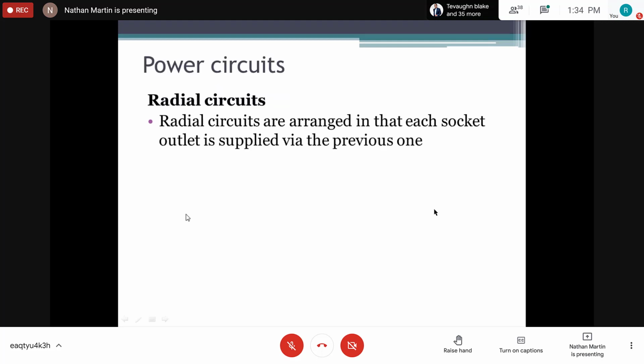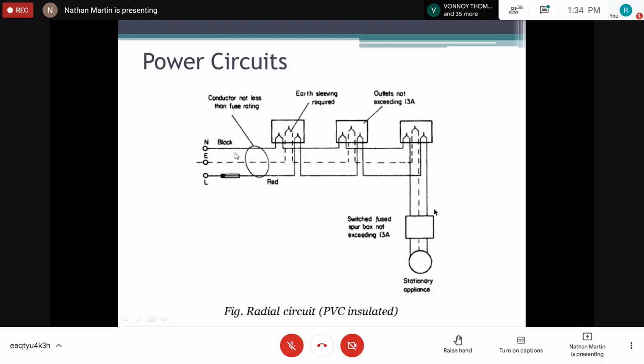So look at this pictorially, right? We say radial circuits are arranged so that each socket outlet is supplied via the previous one. So this also uses a looping method, and this is shown here. We go from our live to our connection, then from our connection to another socket outlet, and then from that socket outlet to the next socket outlet and so on. This is what we term a radial circuit. And if the connection was to break here, then all the circuits beyond this point will not have any power, all right? That's basically the disadvantage of a radial circuit.